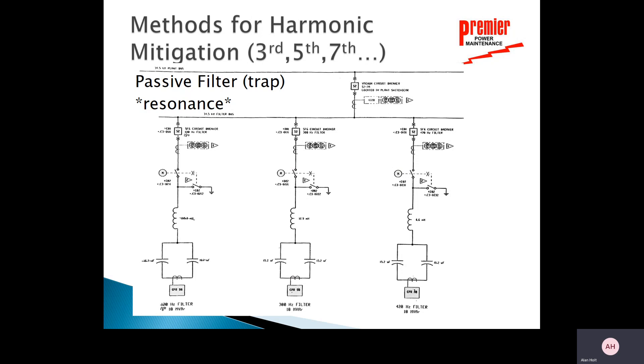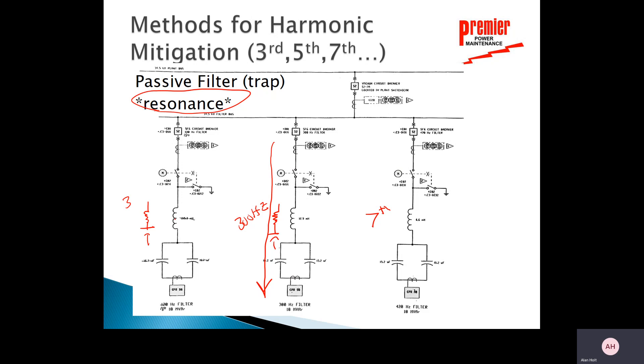Another method is harmonic trap filters — series LC circuits tuned to specific harmonic frequencies. One inductor-capacitor series circuit is tuned to 300 Hz (fifth harmonic), so fifth-harmonic current finds near-zero impedance there and diverts to ground rather than propagating through the system. Similarly, separate traps are tuned for the seventh and third harmonics, filtering those currents directly to ground and keeping them off the utility grid.